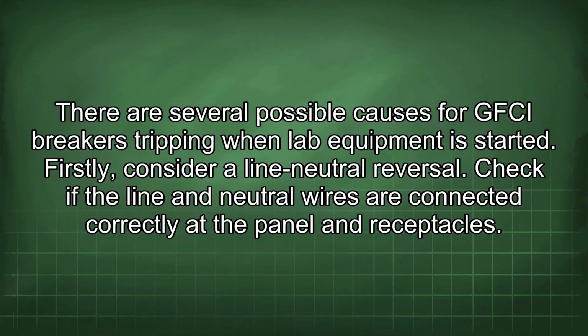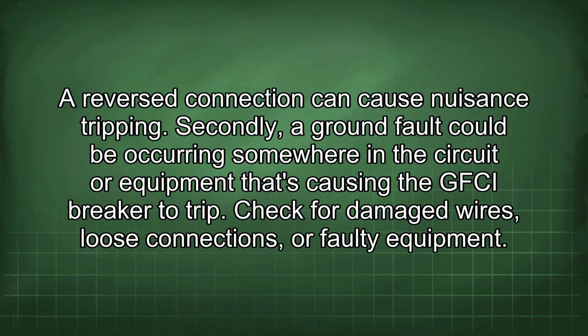There are several possible causes for GFCI breakers tripping when lab equipment is started. Firstly, consider a line neutral reversal. Check if the line and neutral wires are connected correctly at the panel and receptacles. A reversed connection can cause nuisance tripping.